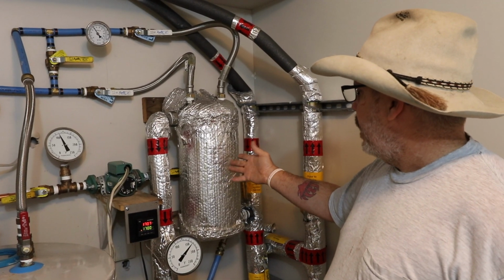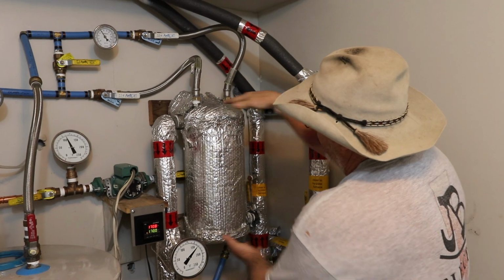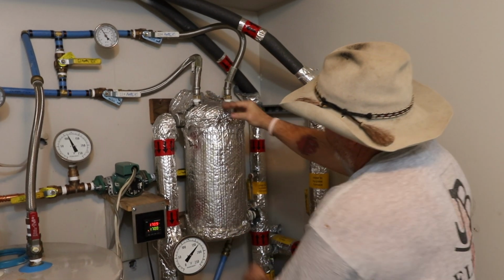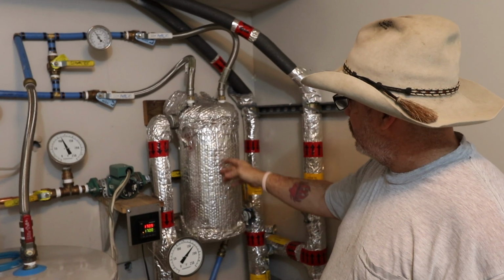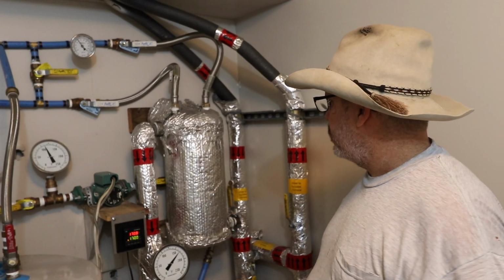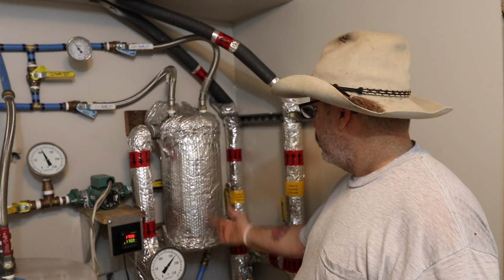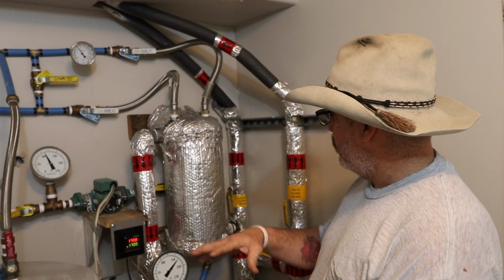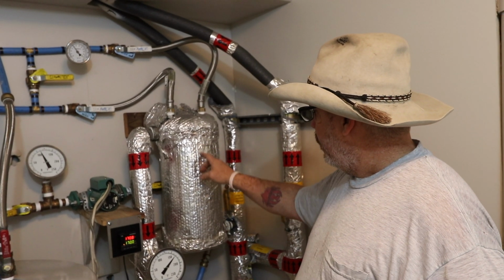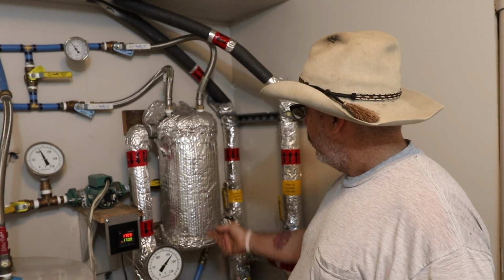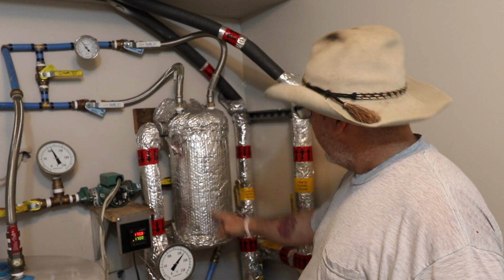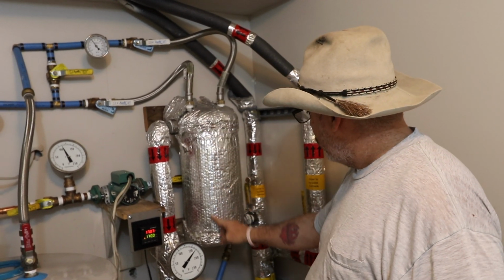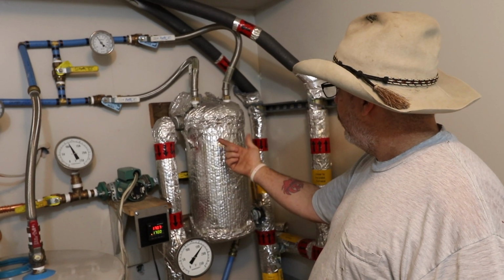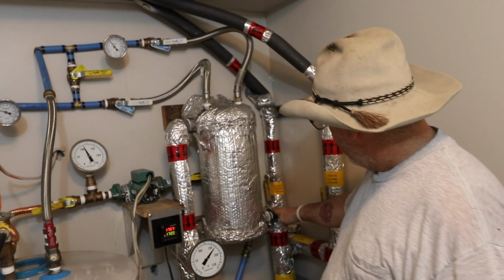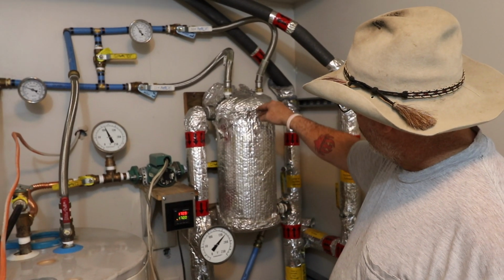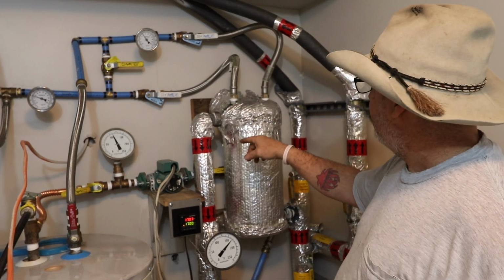All it is is a stainless steel piece of pipe, some stainless steel flat plate. I put a coil in there. That coil consists of 20 feet of 1/2 inch stainless tubing that I coiled up in there. It wasn't a tight coil, it was like a spring coil. And my domestic water goes through that coil. It comes straight down through here and goes down the coil, and then it just starts working its way up, getting heated up with the boiler water that comes into the bottom. The heat rises, so we come into the top and then we go out back to the boiler.